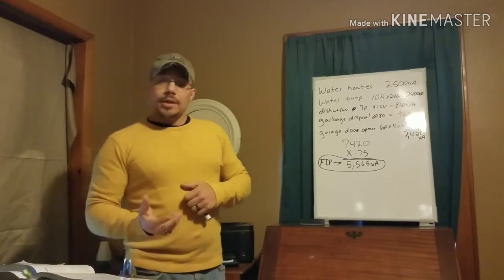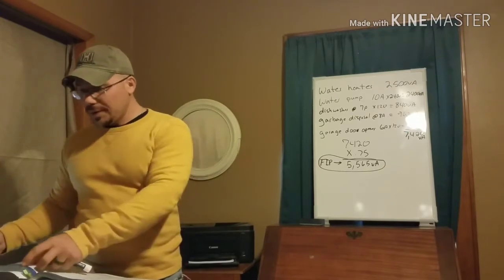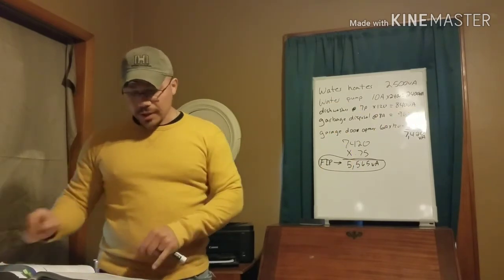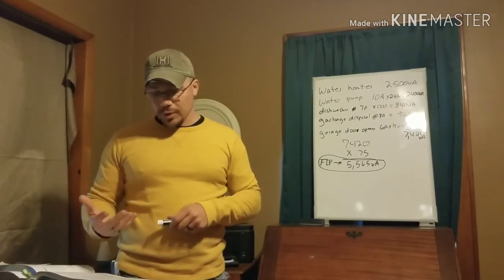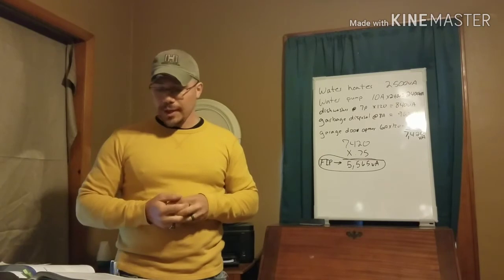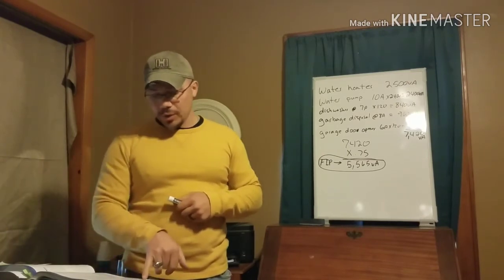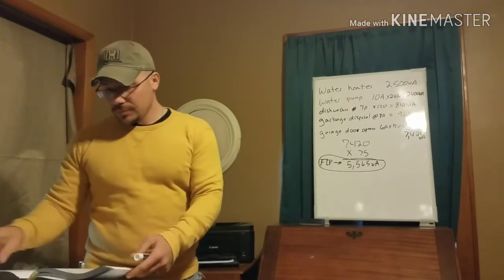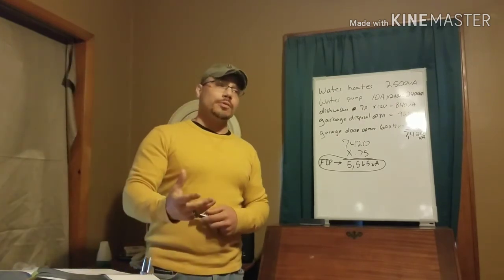The last thing in this video is our motor load. Turn to section 220.50. Section 220.50 says motor load shall be calculated in accordance with 430.24, 430.25, 430.26, and with Article 440 for hermetic refrigerant motor compressors. We're going to look at 430.24, which is the one that really applies to us in service calculations for residences.